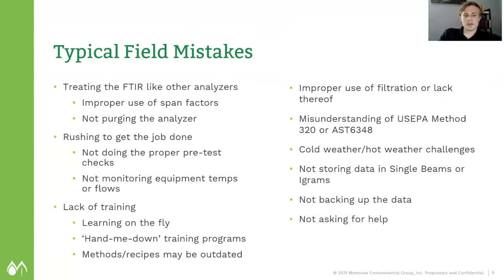So these are our typical mistakes. They're far too common in our industry. We hope that we can eventually sweep these out and get rid of them one day, but one step at a time, just being aware of what the problems are. A lot of firms treat the FTIR like other analyzers. This is a laboratory grade instrument that has been essentially retrofitted for stack testing. Stack testing is difficult, and poor care of these instruments over time really impacts data quality.